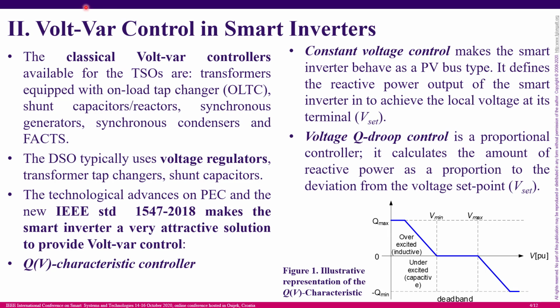For instance, one of the characteristics could be the reactive power-voltage characteristic controller that is represented in this plot. What we have is a dead band with a minimum and maximum voltage, and the converter is not producing any reactive power. But if the voltage goes beyond the dead band, there is a slope, and this slope will produce or absorb reactive power in order to keep the voltage under control. Of course, there is a limit in this control action, and that is the maximum and minimum reactive power that can be provided by the control.